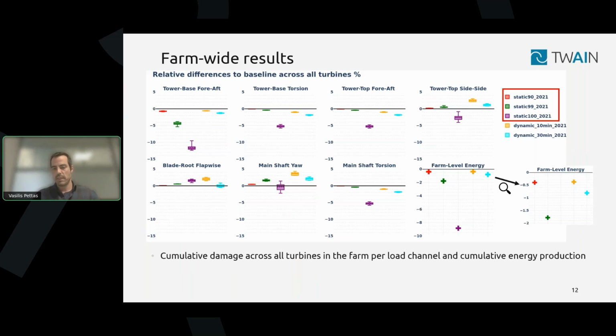When we look at the dynamic case, we see a different pattern: more frequent starts and stops, which translates to higher fatigue increases, but also a lower penalty in energy. With a 10-minute stop interval in the dynamic case, we have about the same energy loss as the static 90 case.